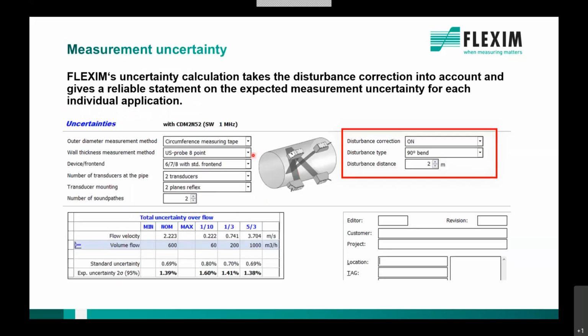So, measurement uncertainty, as I said, for those who are not familiar with the FLEXIM software, you are able to make an uncertainty calculation customized specifically for the application you're dealing with. You enter the diameter, wall thicknesses, how you measured it, transducers you select, the installation you select, and it pops up with an uncertainty. When you have calibrated systems, it can be taken into account that we have a disturbance correction. So if you switch that on, select your disturbance type, enter the distance, the correction factor is used in the background.